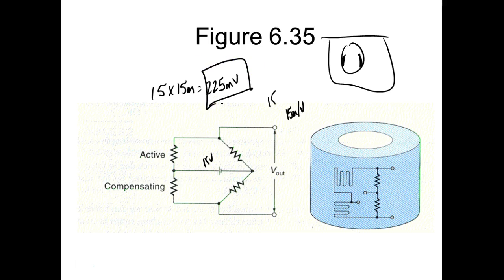So you can see these instruments had to be very, very precise. If I had a 100,000 pound load cell, then that's 225 millivolts divided by 100,000 pounds -- so we're talking about microvolts per pound. And this is differential, by the way, so we're sending two signals, the differential output. It used to really amaze me how accurate these things were.